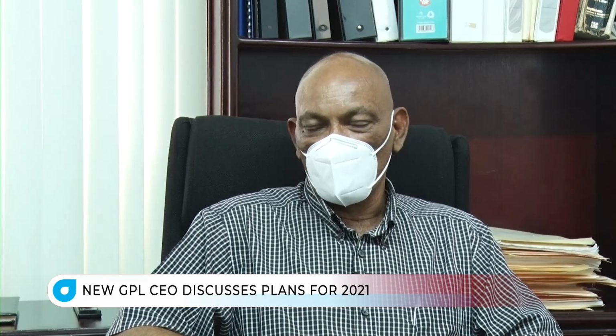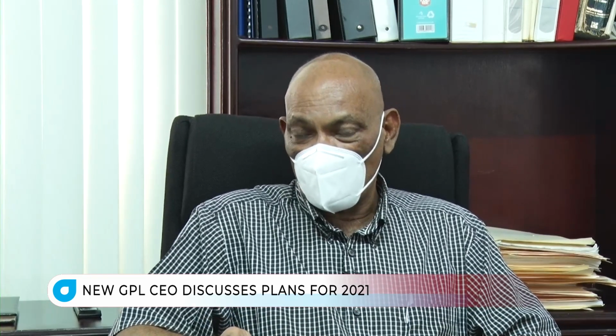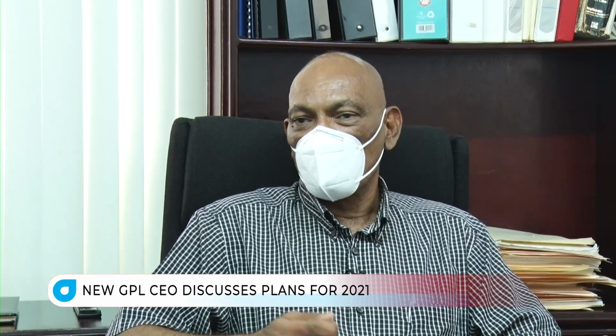Whenever these feeders trip, we go through a process. We try to repower the feeder within a short period of time. You might see your power go off, then in a couple of minutes it comes on, and goes off again. That's us trying to see if there's a transient fault.